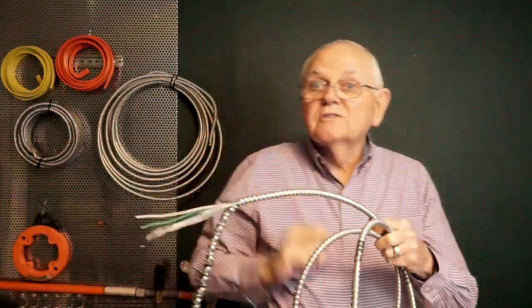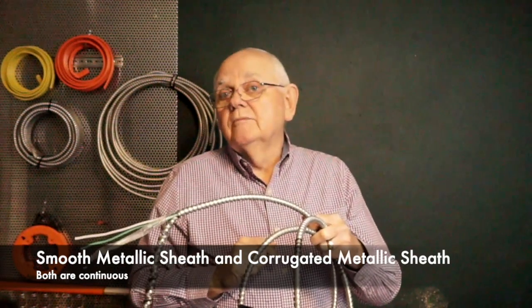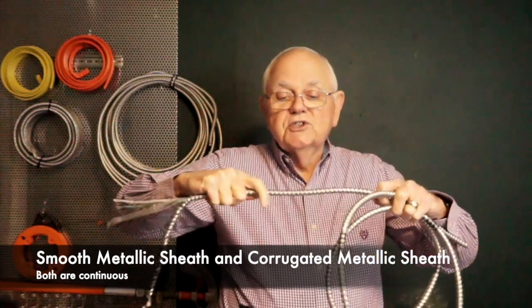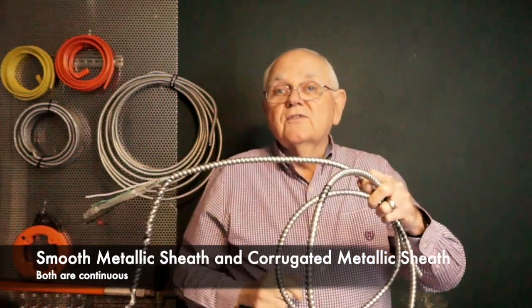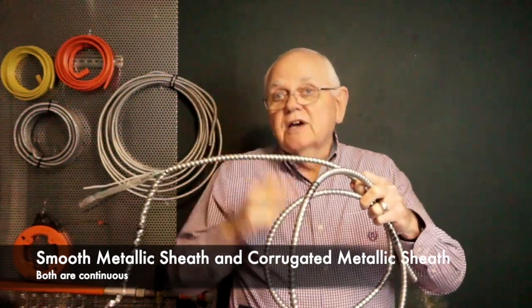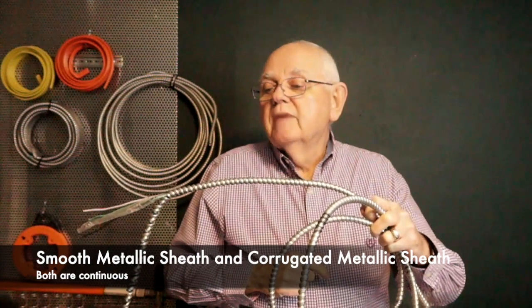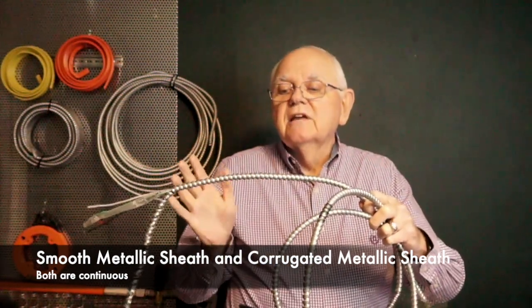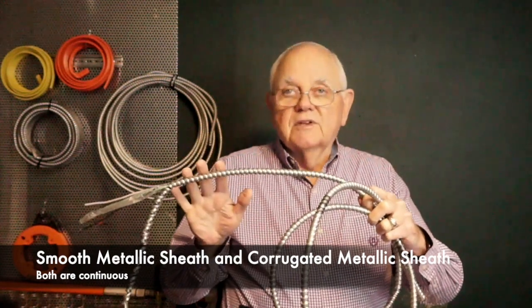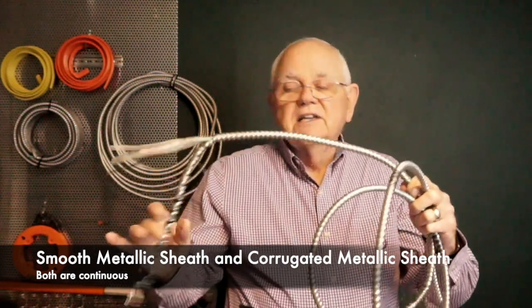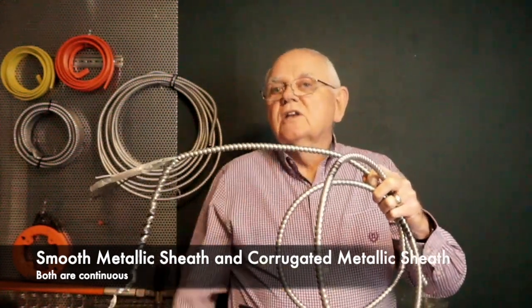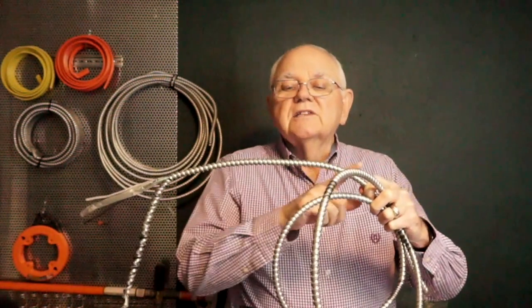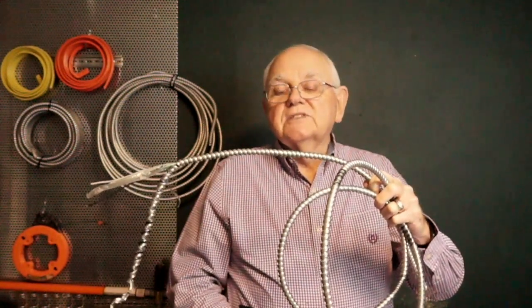Now, there are 2 other types of construction of type MC cable. They're both, think of them as continuous tubes. One has a smooth outer finish, so it's just simply a smooth, continuous metallic sheath. And then there is the corrugated type metallic sheath, where it is continuous. It's not a tape like this. It looks very much like the interlocking tape type, but it's not. It's a continuous corrugated metallic material on the outside of it. So anyway, 3 different types of construction. And that's going to make some differences in applications and so forth.